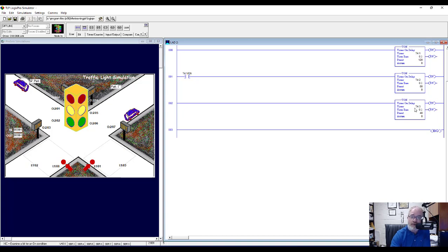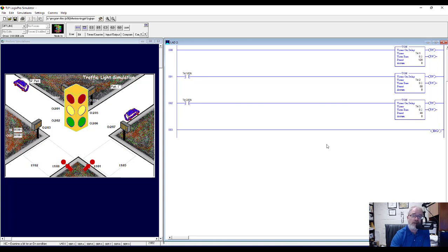The third timer needs to start when the second timer is done. So we get another examine-if-closed: T4:2/DN — the second timer's done bit — which will start the third timer. The first timer starts immediately when we run the program, and then when it's done it starts the second timer, and then when that's done it starts the third timer.